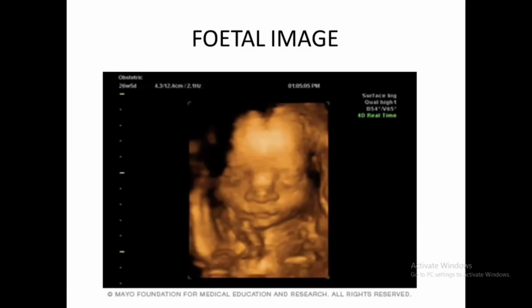See, generally, any service engineer who goes to fix an ultrasound machine or for installation should, before any installation, check for earth. It depends upon each area, each country, each place. We might not know how exactly earth, neutral and the mains work, so you should check for that. If you fail to check the earth, the machine gets a short. It starts giving a short fault.